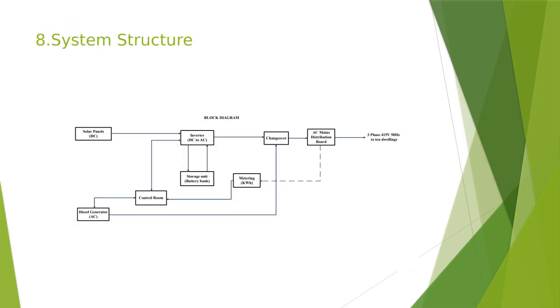Then on the system structure, it was shown as a block diagram. We've got solar panels which supply DC power to the inverter, and the inverter converts the DC to AC, and it goes through the changeover switch and then to the distribution board. Then from the distribution board, we supply our 10 dwellings. Then the inverter also charges the batteries, and it will be communicating with the control room.